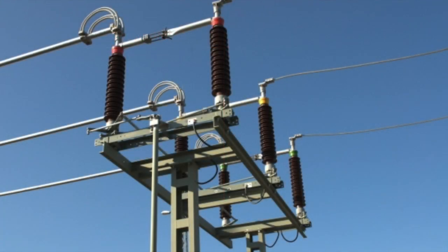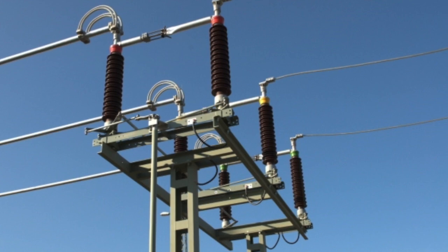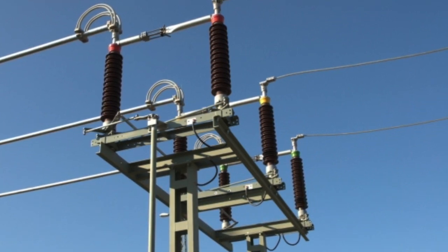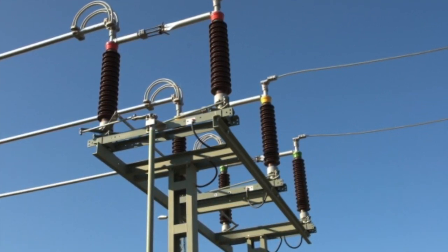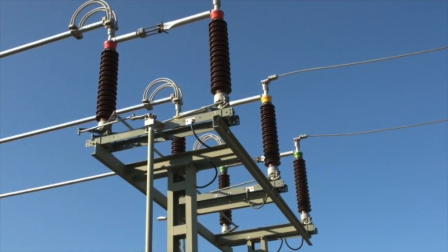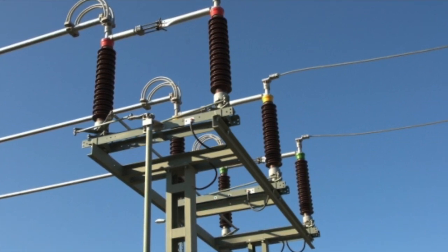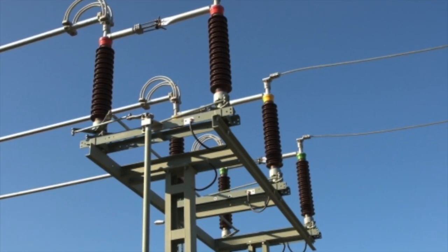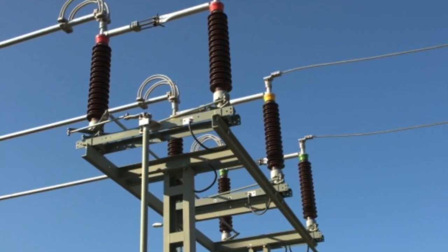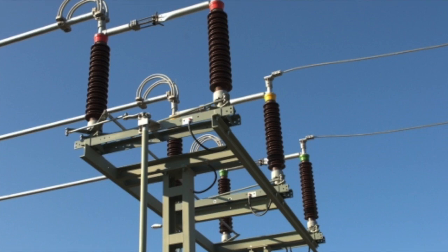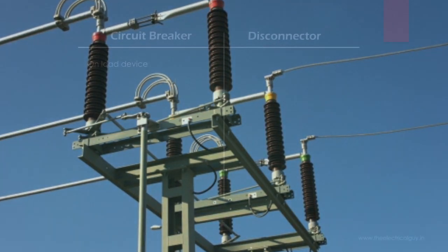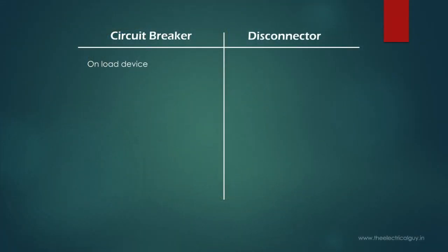Whereas disconnectors or isolators have no ability to break normal or fault current. We can only operate disconnectors in current zero condition, that is when the supply is off, and hence disconnector is called as an offload device.